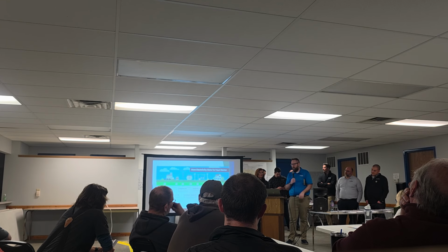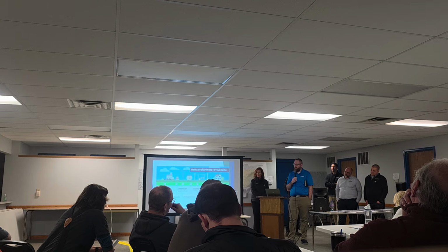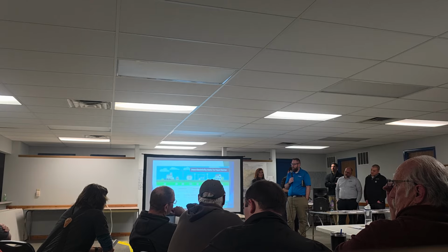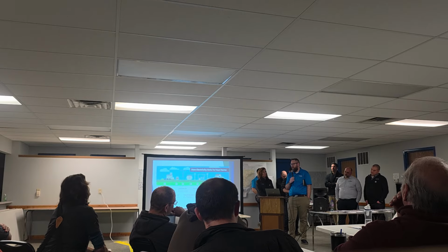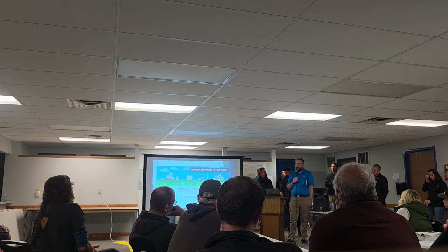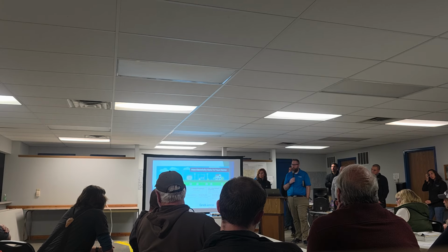And those overloads, when we're talking about reliability issues, that's what a reliability issue is: when you've overloaded a line and it's gonna trip itself out, and then those can cascade as you keep losing more and more elements across the system. So without this line, you would see a significant increase in flows on the 161. And so by creating the 765, you do indeed unload the 161 to provide more flexibility to other uses. I think if we had the space till 8, we're at 8.